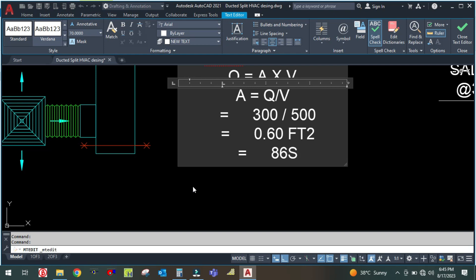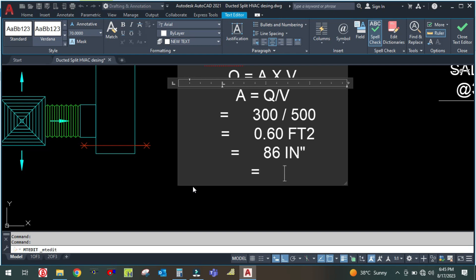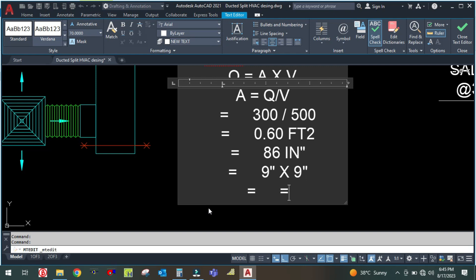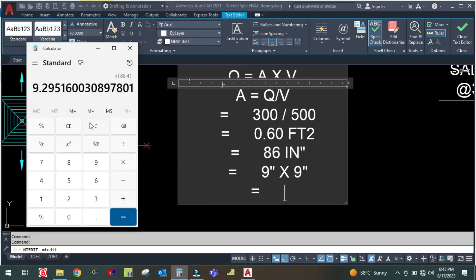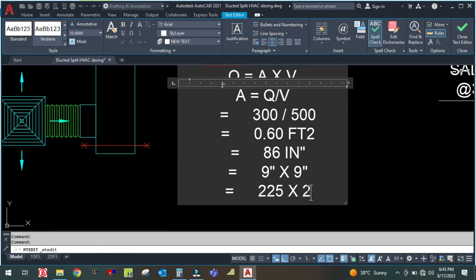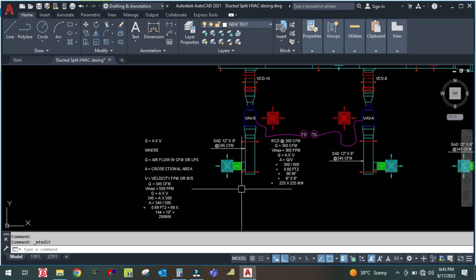So we have 86 square inches. Taking the square root of 86 gives approximately 9 inches. So the return ceiling diffuser is 9 inch by 9 inch. Converting 9 inches to mm — since 1 inch equals 25 mm — we get 225 by 225 mm as the size of the return ceiling diffuser.